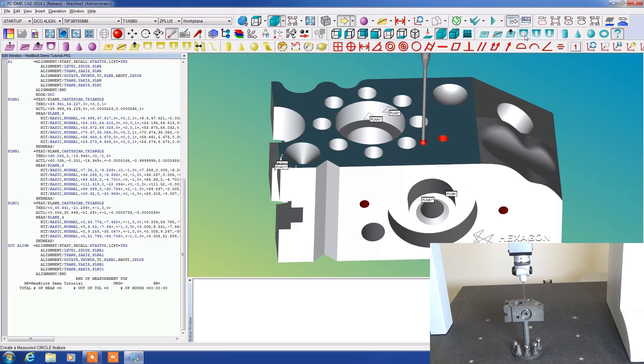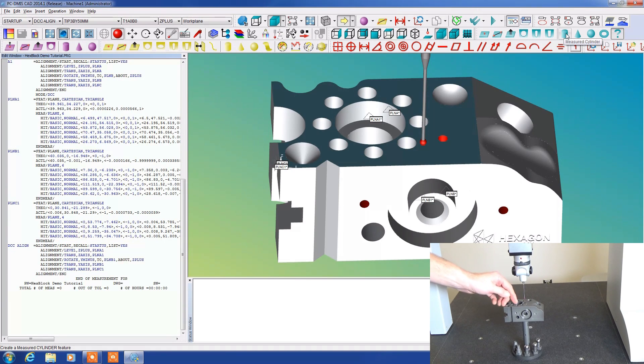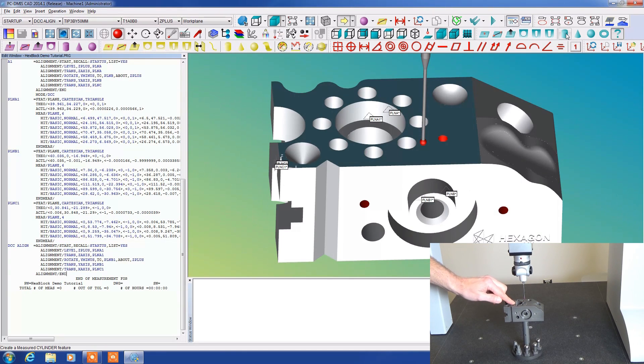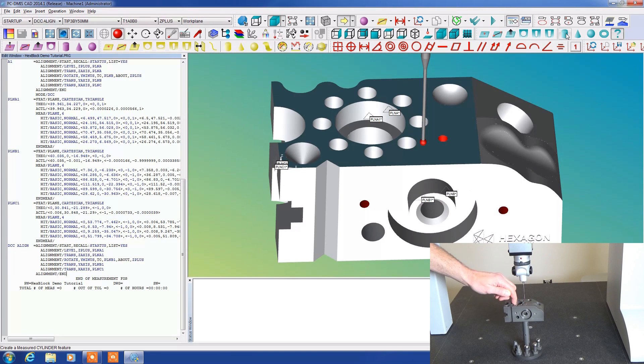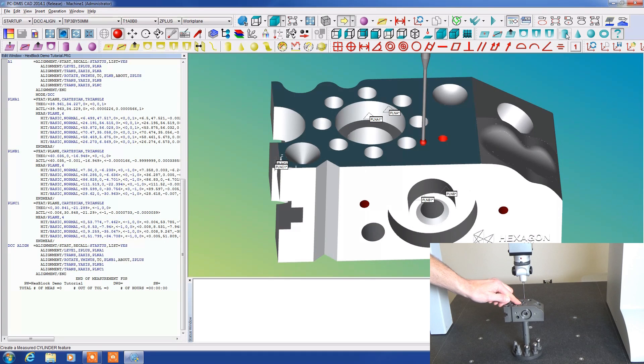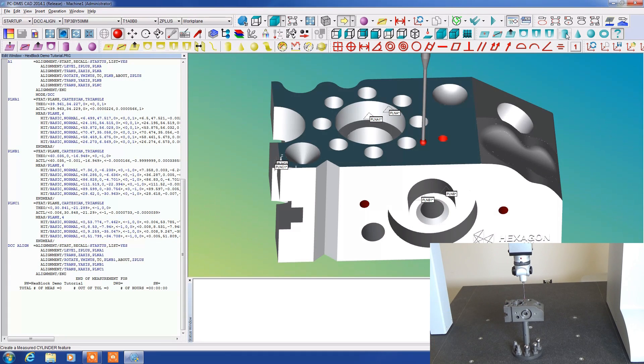However if we're looking at a measured cylinder, for instance the center of this here, we need to have three hits in the same plane at the top and then three hits below it not in the same plane. Typically they should all be at slightly different levels in there and then it will know that it is a cylinder.